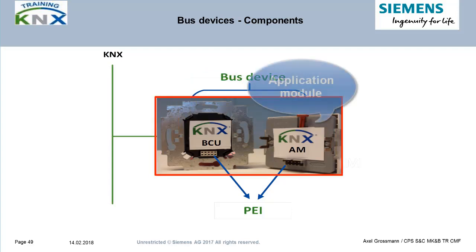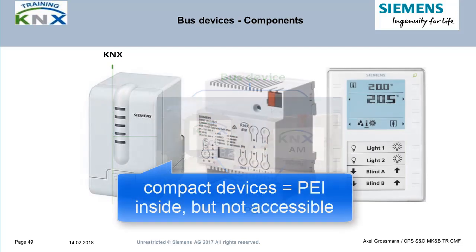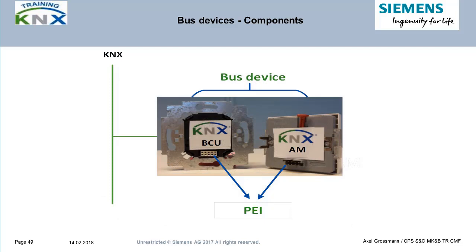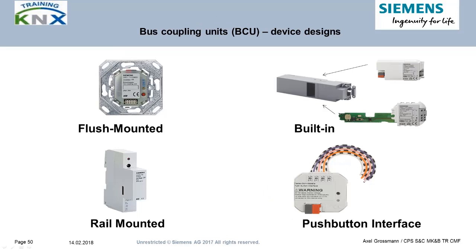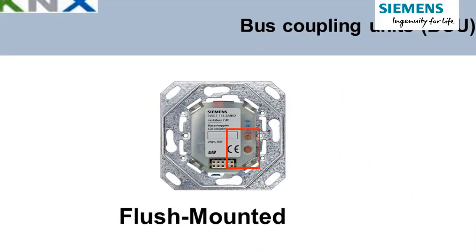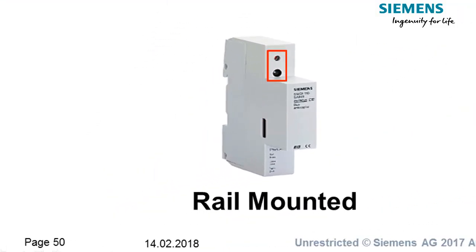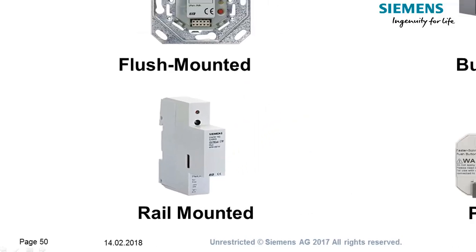In principle, bus devices consist of an application module and a bus coupling unit connected by the PEI. Often these parts are already assembled and fixed to each other by the manufacturer to form one single unit, so there is no accessible PEI anymore — though internally it still exists. On the flush-mounted BCU you can see the PEI, program button, and program LED. The same is true with the rail-mounted version. Both BCUs are the so-called universal classic type, which were once sold by all KNX manufacturers and would have been exchangeable in principle.